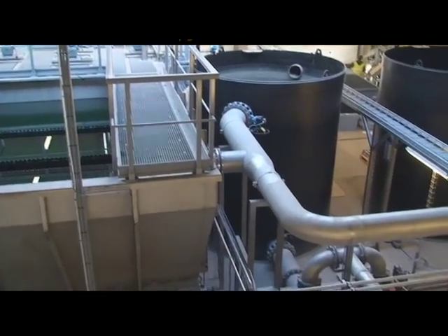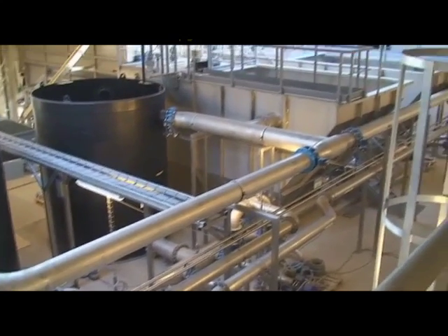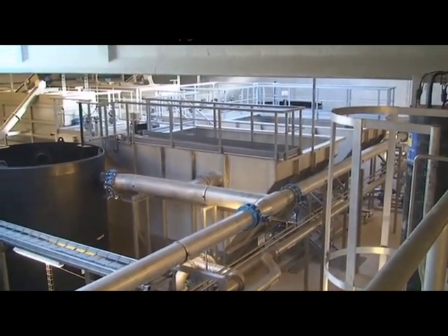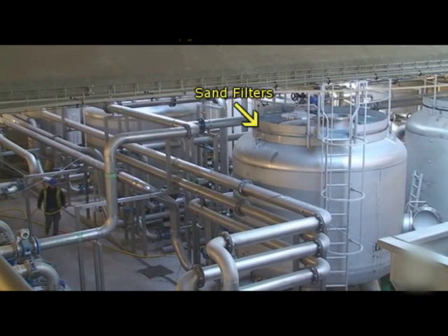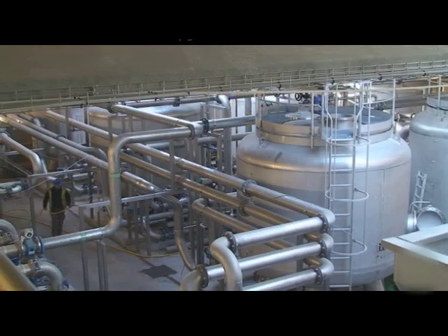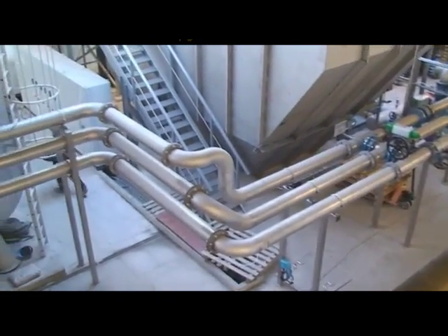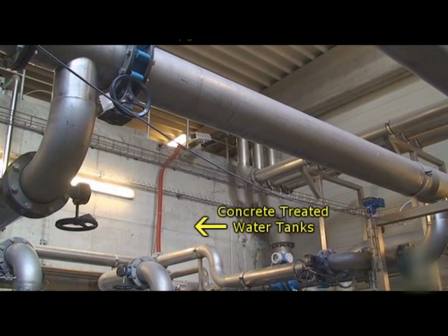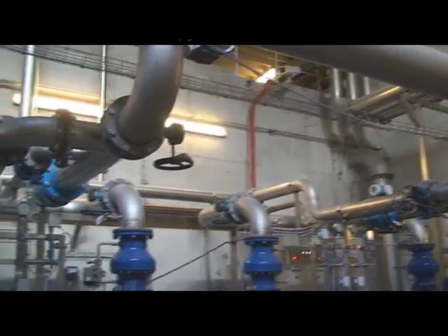The piping to the various tanks and process equipment within the plant is interconnected for redundancy and concurrent maintainability. Duplex pumps are used to pump the clarified water into sand filters. The water trickles through the beds of sand in the filters and is further clarified in this process. The treated water is stored in three above-grade water tanks where chemical treatment takes place to control microbial growth.